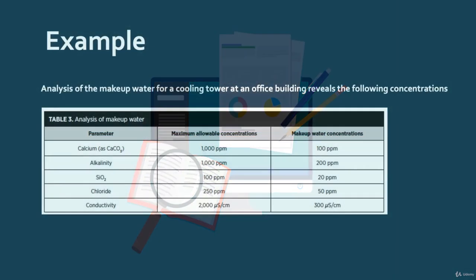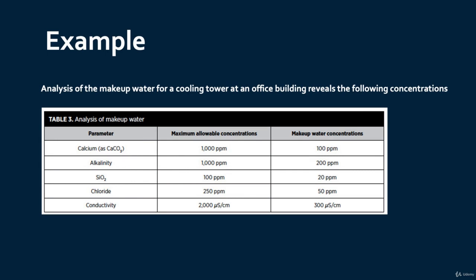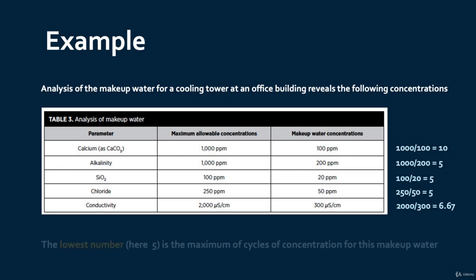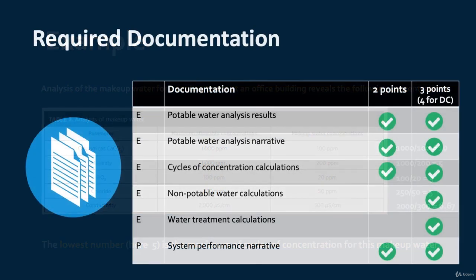Now let's have a look at an example before we close this section. Here you see an example of an analysis of the makeup water for a cooling tower at an office building, and it reveals the following concentrations. As you see for calcium, for example, the makeup water concentration is 100 ppm. For alkalinity, 200 ppm. So how do we calculate the number of cycles? Basically, we divide one by the other. So 1000 divided by 100 for calcium, and for alkalinity, 1000 divided by 200 is 5. We go through that list, and the lowest number, here the number 5, is the maximum cycles of concentration for this makeup water. Pretty straightforward. Now let's have a look at the required documentation.